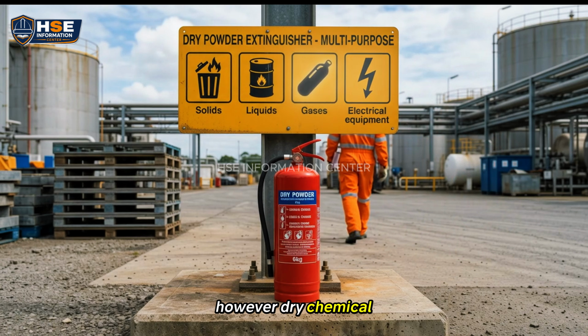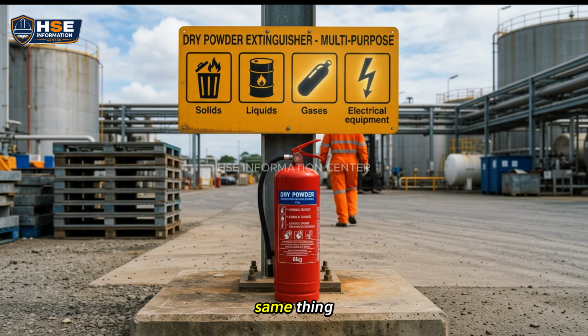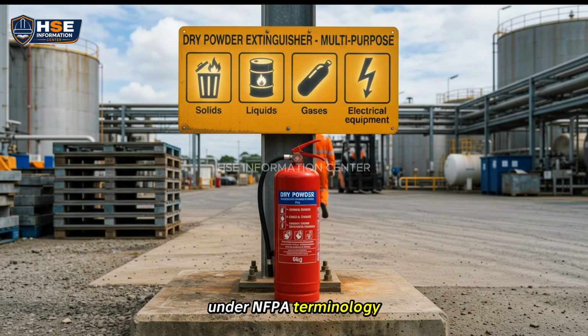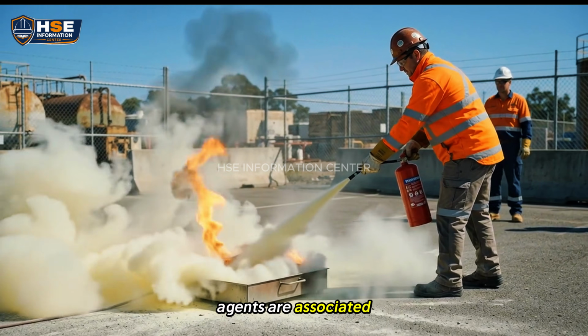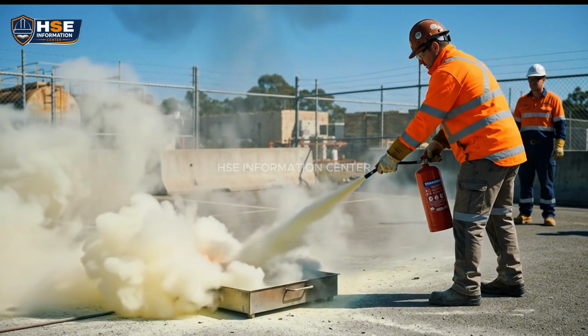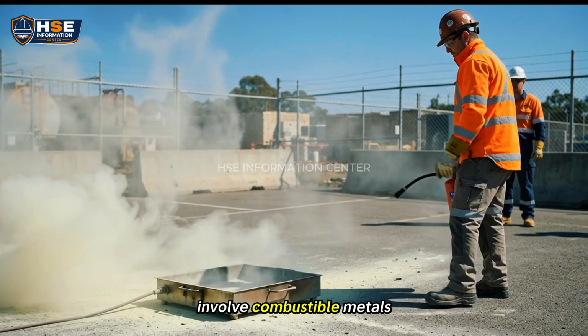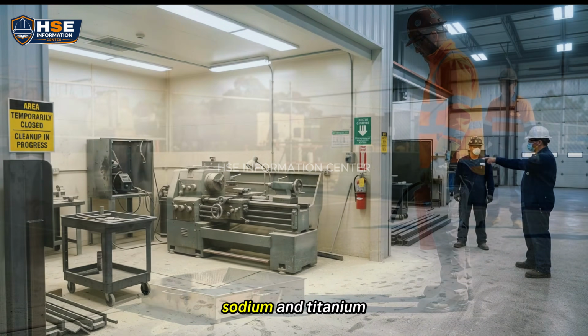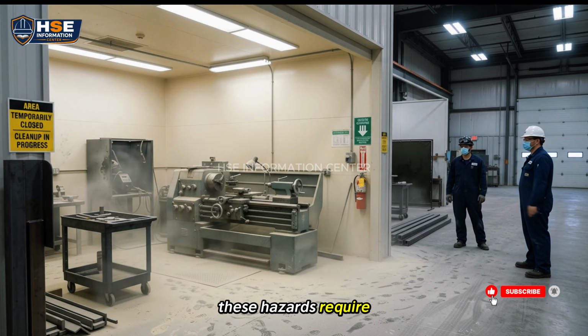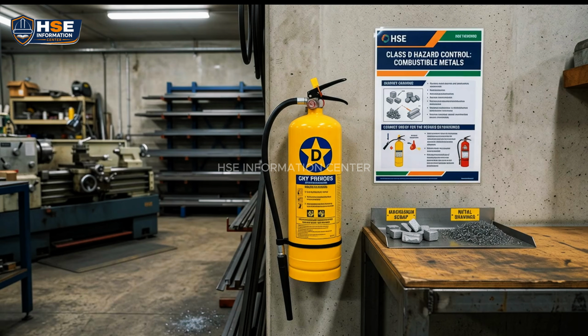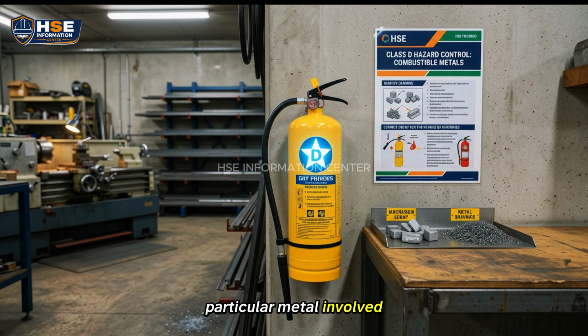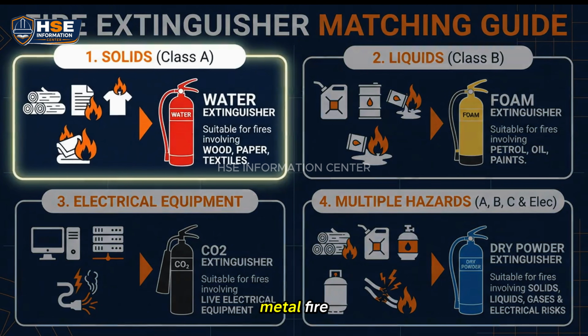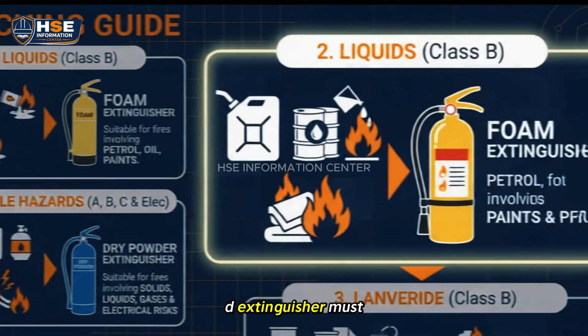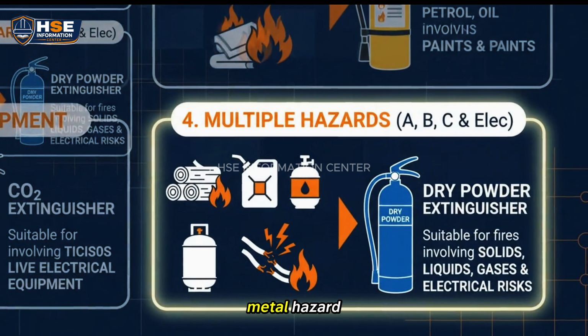However, dry chemical and dry powder are not the same thing under NFPA terminology. Dry powder extinguishing agents are associated with Class D fires. Class D fires involve combustible metals such as magnesium, sodium, and titanium. These hazards require specialized extinguishing agents designed for the particular metal involved. A normal ABC dry chemical extinguisher should not automatically be considered suitable for a combustible metal fire. The correct Class D extinguisher must match the specific metal hazard.